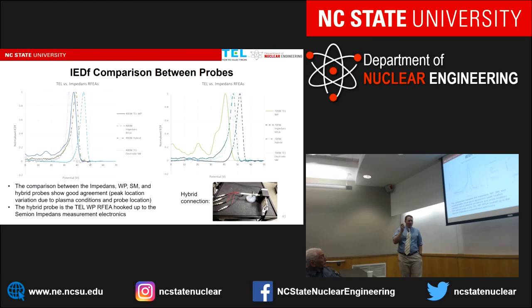So we've talked about the IV curves. How is the actual operation of the RFEA working? In this instance, we have some IEDFs where we compared the wall probe and the surface mount probe, one that's just a millimeter below the surface of the electrode, to a commercial system, a Semion RFEA system done by Impedans. As you can see, the normalized IEDFs, the shapes in general are pretty consistent. There is some variability in the peak location, but it's possible that's due to plasma non-uniformity or the location of the actual RFEAs.